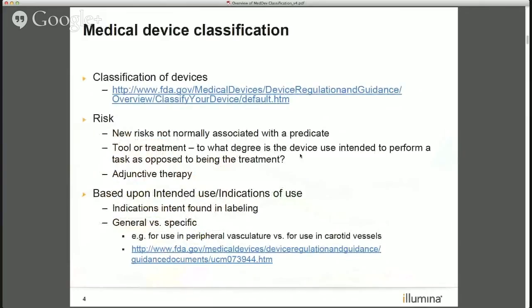Starting with device classification, here's a link to an FDA site that goes into classification in detail. A major factor that FDA uses to determine device classification is risk. If your device presents any new risks compared to a device currently on the market — also known as a predicate — that is something they'll take into consideration for class determination. Whether your device is a tool or a treatment can also impact whether it's high or low risk, and an adjunct therapy to a diagnostic is probably going to be lower risk than a sole treatment device.